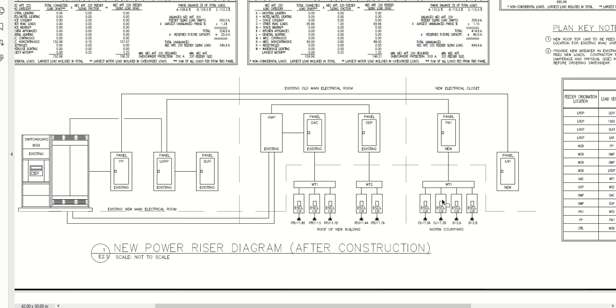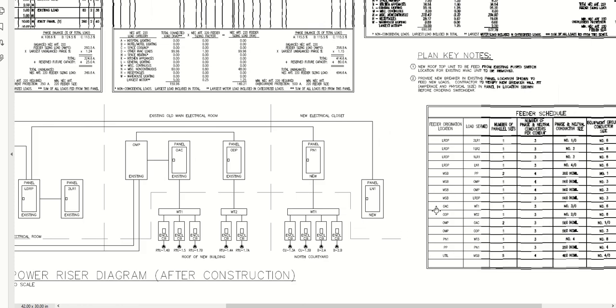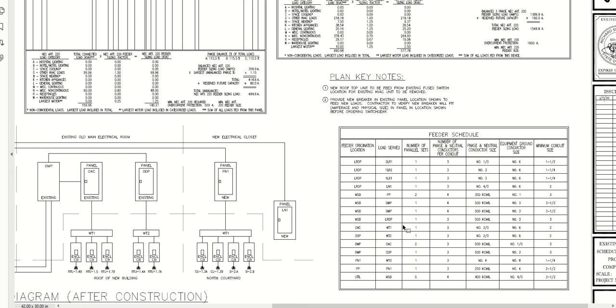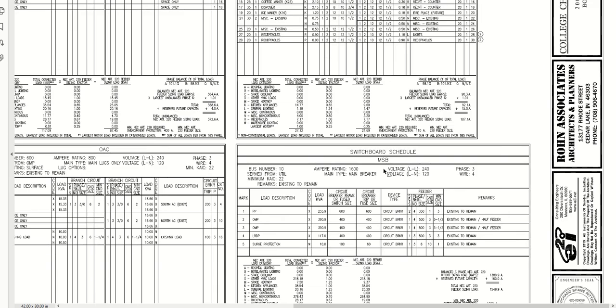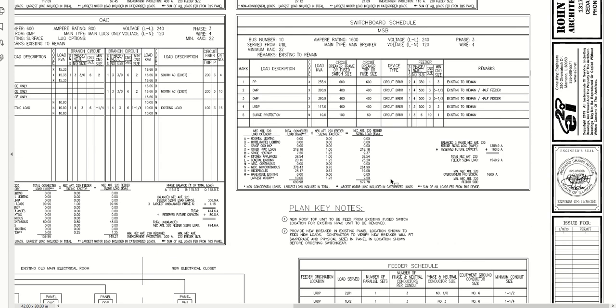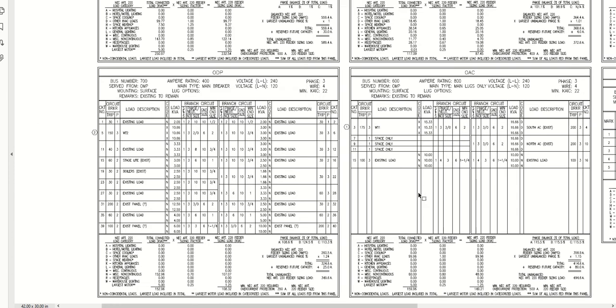We show the division of where everything is. Here's our feeder schedule that shows from the originating location to the load served what we're running. Each of these lines should have representation in this feeder schedule. Here's our switchboard schedule—this shows with the new load it's a 1600 amp board. After we add all the new load and revisions, even with 160 future, we're still well below the main rating so we should be good on that.